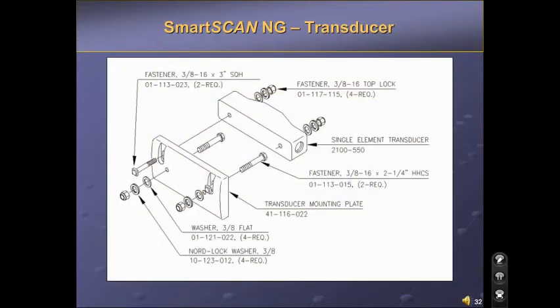One of the most frequent complaints regarding transducers is that they do not stay tight on the rail. STC has put together a group of locking hardware that has proven to be very effective in this regard. Each transducer comes with bolts, Nord-lock washers, and nuts. It is important to use all of this hardware correctly.